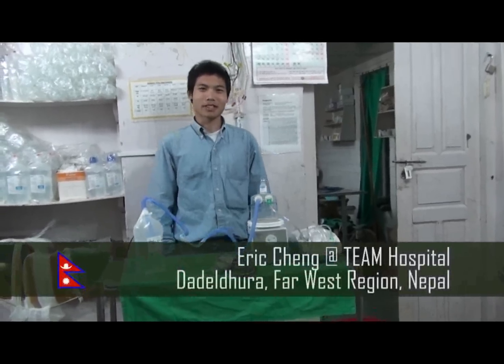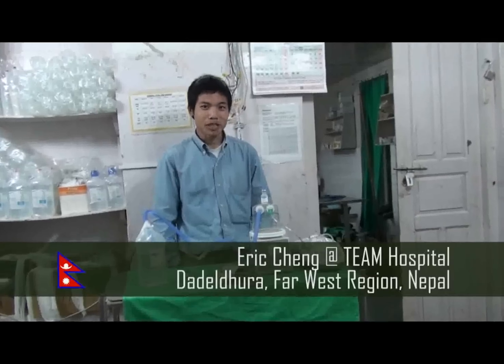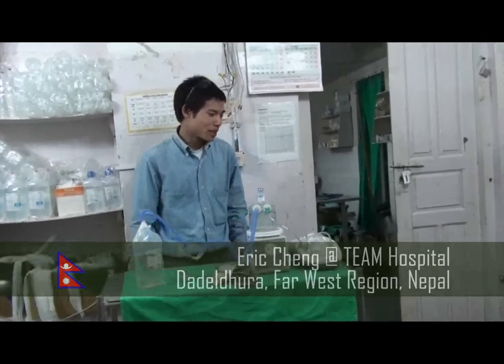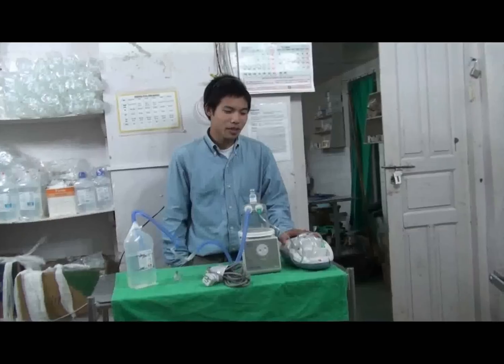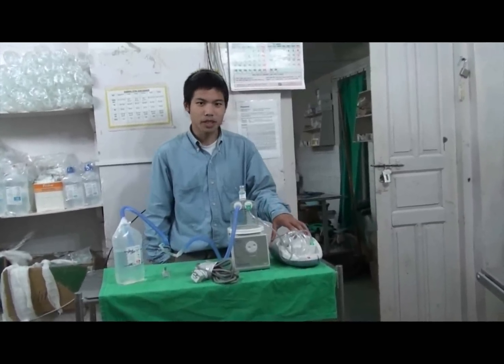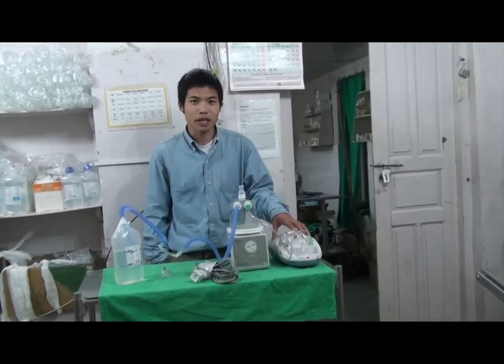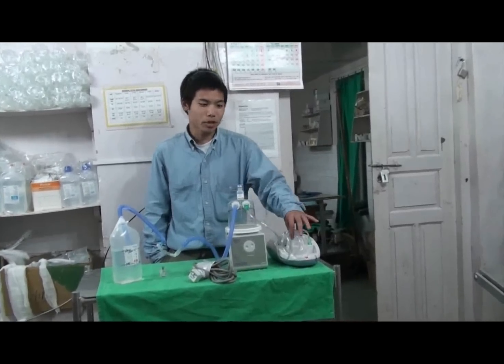Welcome to Team Hospital in Dadeldhura, Far West Region, Nepal. Here we are demonstrating a bubble CPAP system that we've set up here. We're using a nebulizer because oxygen is very hard to get to in this place, and also it reduces the risk of ROP in the premature babies.